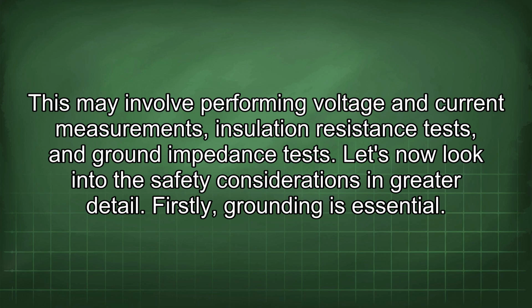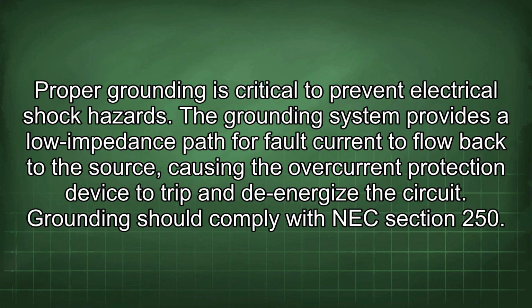Let's now look into the safety considerations in greater detail. Firstly, grounding is essential. Proper grounding is critical to prevent electrical shock hazards. The grounding system provides a low impedance path for fault current to flow back to the source, causing the overcurrent protection device to trip and de-energize the circuit. Grounding should comply with NEC section 250.